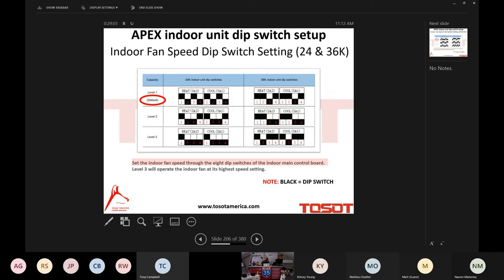So the indoor unit, you're going to set the indoor fan speed switch. Now, this picture is another reason I could never claim being the sharpest tack in the box. Because when I saw this diagram in the service manual, I said to myself, wow, that's a lot of dip switches. I went looking for 12 sets of dip switches. And I'm happy to say I'm not the only guy who has done that, including Wes and Dennis and brilliant people associated with this product. There's only one set of eight, right?